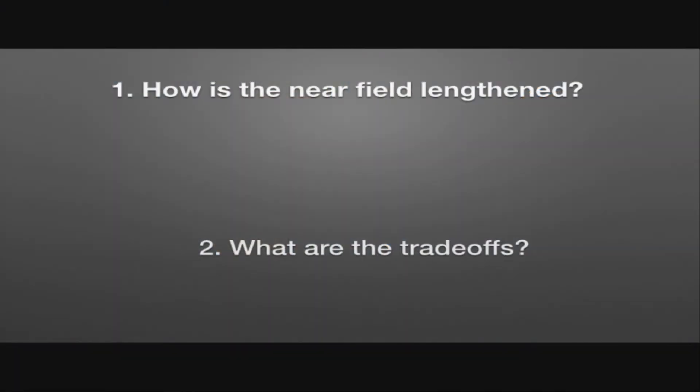So let's ask a couple of questions. First of all, how is the near field lengthened? And secondly, what are the trade-offs of this? Well, as we just discussed, the length of the near field is related to aperture squared divided by 4 times the wavelength. So therefore, to lengthen the near field, we can increase the frequency, or increase the size of the transducer. But what are the trade-offs of doing this?